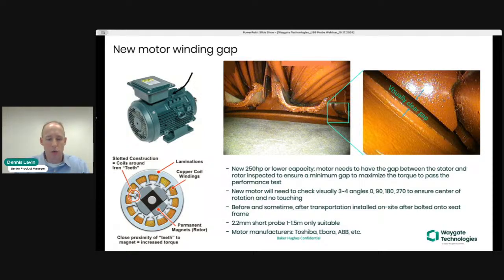So technicians will go in. They'll inspect 3 or 4 different angles at 0 degrees, 90, 180, 270, just to make sure that rotor center and the gap is adequate clearance. So if you look at the borescope image here up top, you can see kind of the wide angle look where that gap is, and then the close-up view that was taken with a small diameter probe to make sure you have adequate clearance there.